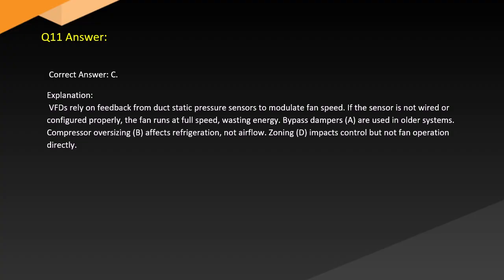Answer. Correct answer: C. Explanation: VFDs rely on feedback from duct static pressure sensors to modulate fan speed. If the sensor is not wired or configured properly, the fan runs at full speed, wasting energy. Bypass dampers, A, are used in older systems. Compressor oversizing, B, affects refrigeration, not airflow. Zoning, D, impacts control, but not fan operation directly.